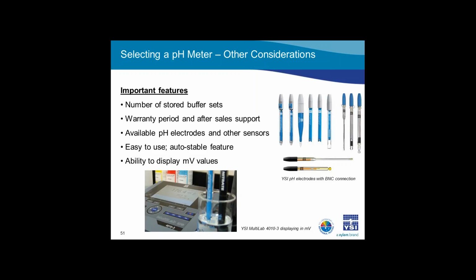Also ensure the meter has a variety of pH electrodes available and that the meter is easy to use. This can be done by checking out reviews, a video overview of the meter, as well as other videos where the meter is actually being used. Instrument auto-stable will ensure calibration and measurement points are not recorded until the measurement is stable. So this is another important feature to consider. Finally, ensure the meter can display millivolt values, as this is an excellent troubleshooting tool when trying to determine any electrode issues.